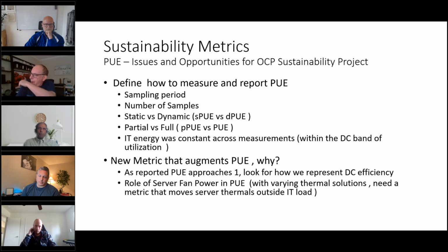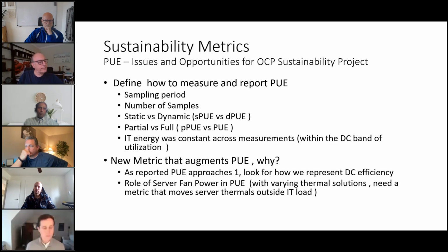If you run it, under these conditions, this is what the PUE would be - versus dynamic PUE, which is what big data centers like Google or Meta report. They're running the data centers, measuring the power, and reporting their numbers. So somebody saying a static PUE of 1.1 is not a fair comparison against someone from Meta saying their PUE is 1.12. It's not at all, because you never ran it, so you will never get that number - there are lots of efficiencies you don't account for in a purely spreadsheet analysis.